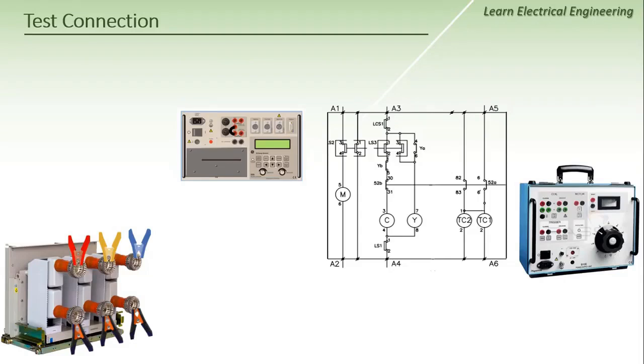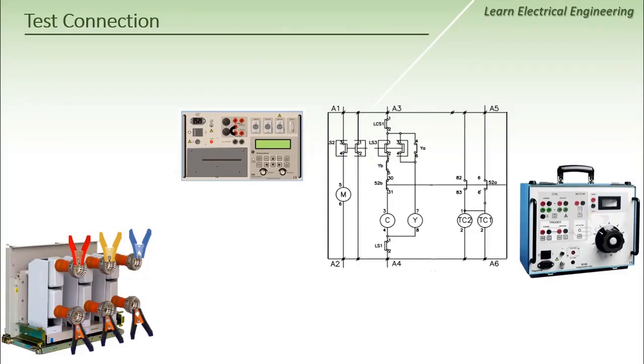Let's see together now how I can perform a circuit breaker timing test. To perform a circuit breaker timing test, I need two things. The first thing is the breaker analyzer test kit, and I will use the EGIL device from Megger Company. Through the breaker analyzer test kit, I can issue different operating sequences for the circuit breaker, such as close open, and open close open. I can also receive feedback from the main poles of the circuit breaker. Using the commands along with the feedback I receive from the main poles of the circuit breaker, I can calculate my timings. The second thing is the control supply voltage.